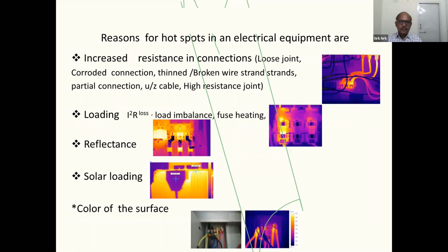We use thermography extensively for electrical system monitoring. Some of the reasons that lead to temperature rise in electrical things are loose joints, corroded, thinned or broken wires, improper connections, undersized cable and high resistance joints. These may lead to heating of the electrical components. Similarly, if the load is not balanced in the circuit, or the fuse rating is not proper, there will be heating on the fuse. You can see this in the image: on the left side, one phase is heated more, either by overloading or by other reasons.